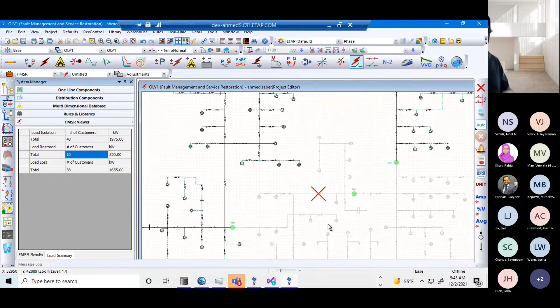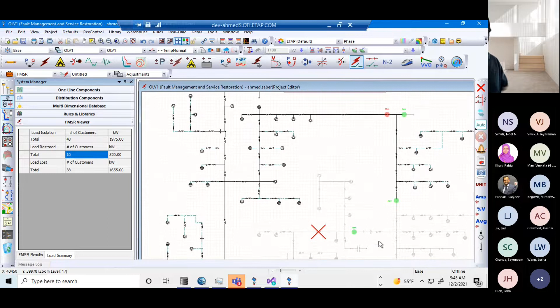So what happened is the system did not restore all the parts, only this part, and the report shows in detail why it didn't restore everything. It shows initially we lose around 48 customers and 1.9 megawatts of load, but after restoration we restored 0.32 — we did not restore the rest because of the thermal limit.